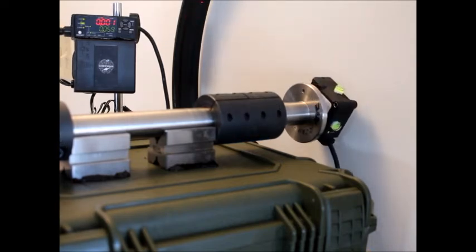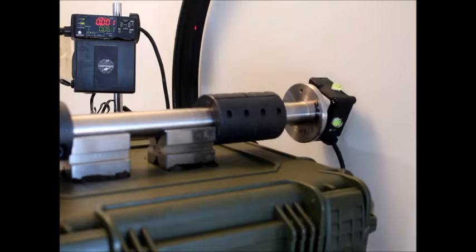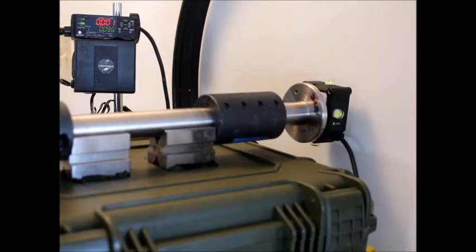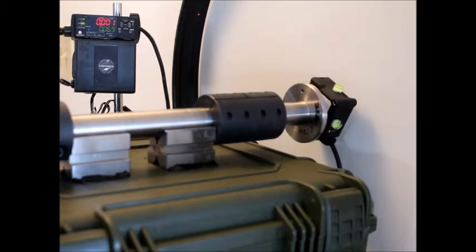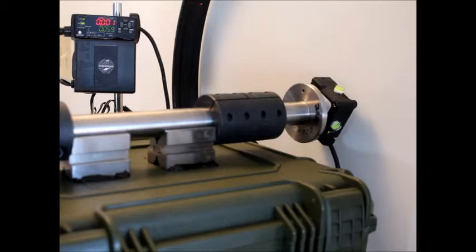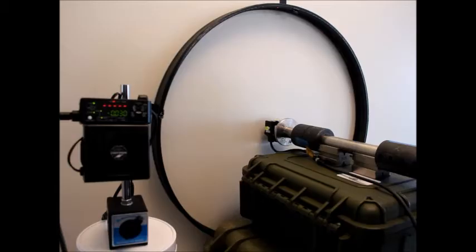Here the delta laser has been attached to the far end of the shaft and is aimed at the ID of this 20 inch rim, making it a 10 inch radius to any point plus or minus any run out, assuming the shaft and rim are centered together.